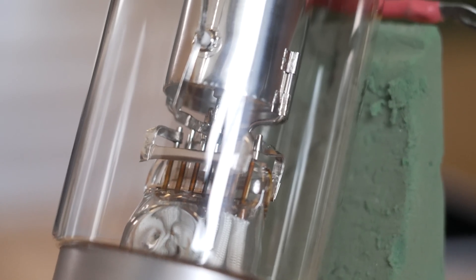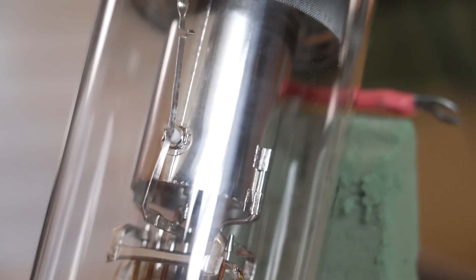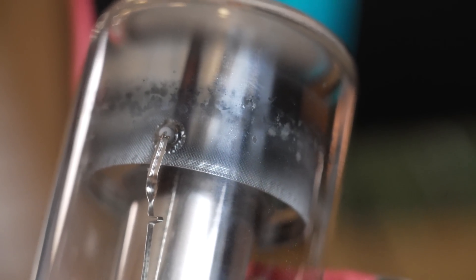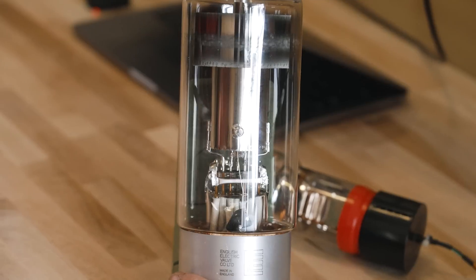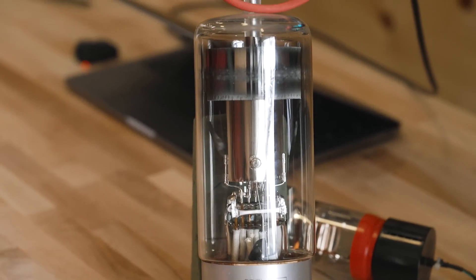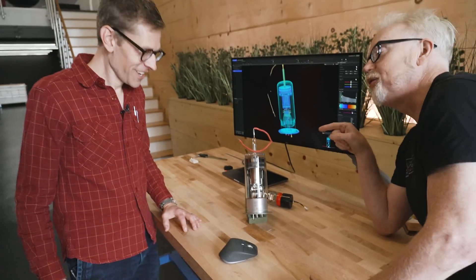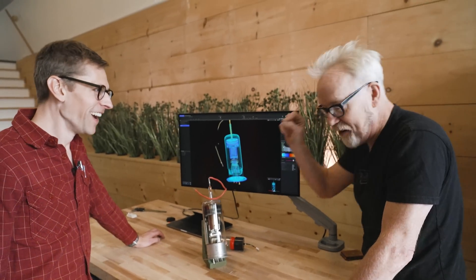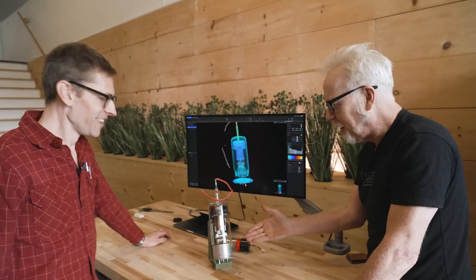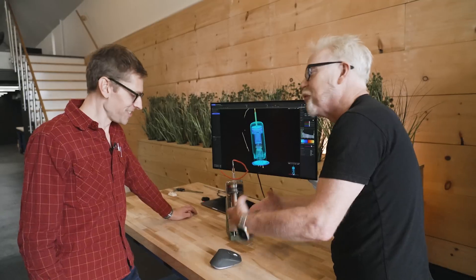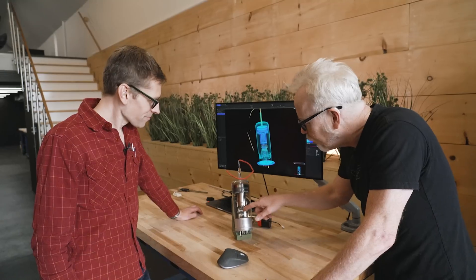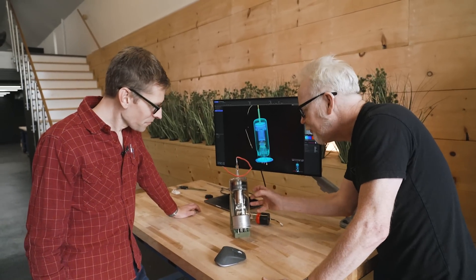Okay. You were saying earlier, and this was totally fascinating to me, that this thing can generate its own hydrogen? That's right. Yeah, so what I believe is going on here at the bottom - I'll explain kind of the theory of operation for the rest of the tube, but down at the bottom there's these little metal tubes with electrical connections at either end, and I believe those are full of titanium hydride powder, which is a material that when you heat it will actually give off a pure form of hydrogen gas. The reason for that is that this tube needs to have a certain amount of hydrogen inside in order to function, but hydrogen is very small and it will leak out of every tiny seal in this device over time. So if you want it to last a long time, it needs to be able to resupply its own hydrogen. Oh my god, my mind is totally blown, because I've always known this about helium, right? You can't draw a perfect vacuum on earth because helium atoms will find their way through the metal because they're so small. And of course hydrogen, being lower on the periodic table, of course they would do the same thing. But somehow I've never - it's never occurred to me that hydrogen would also leak in or out. It's an even harder problem. Yeah, amazing.